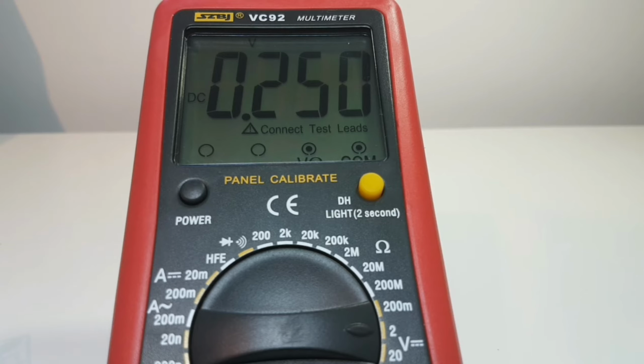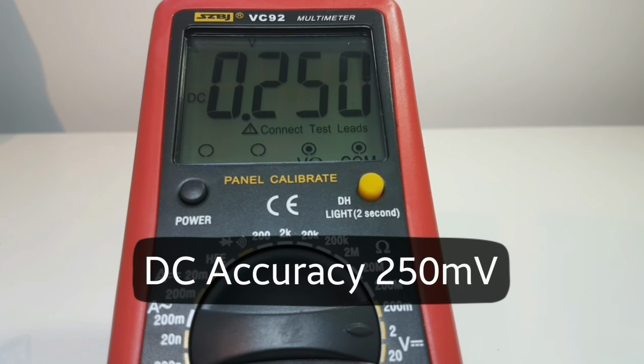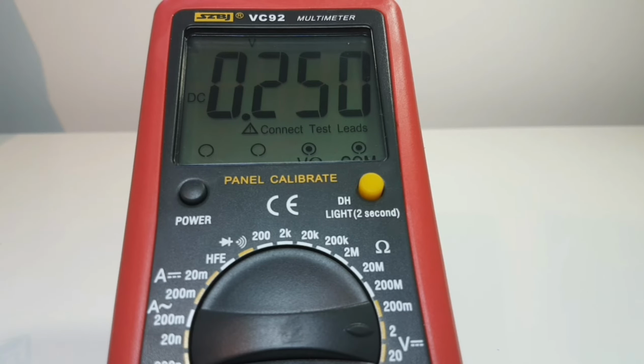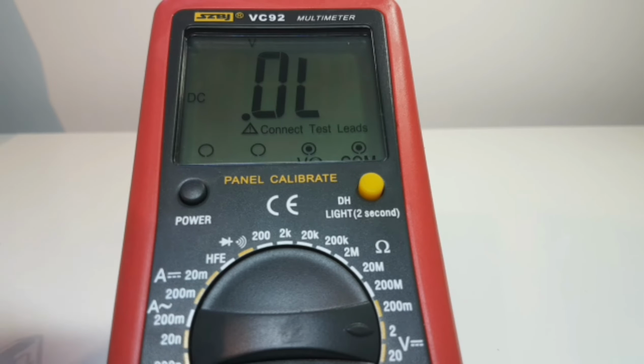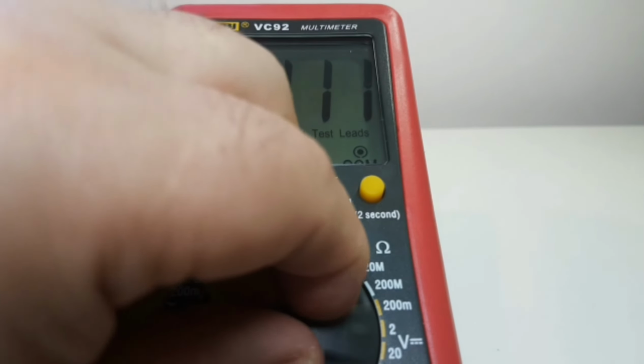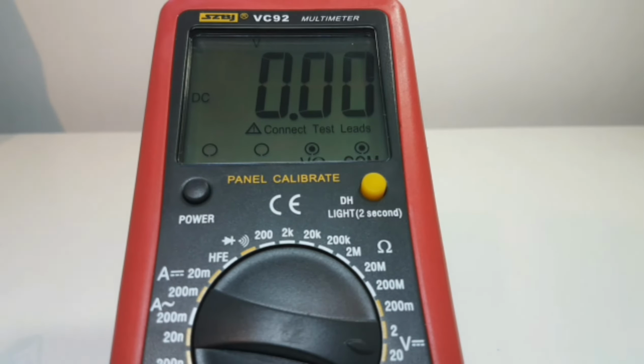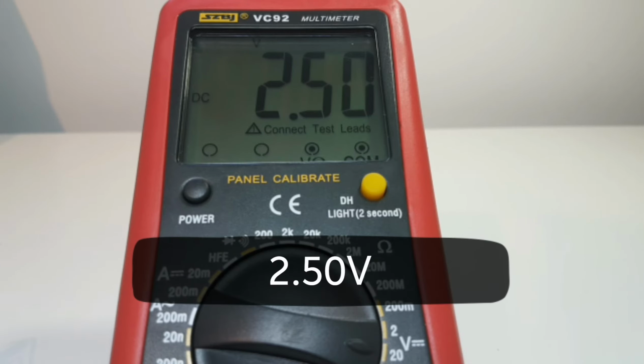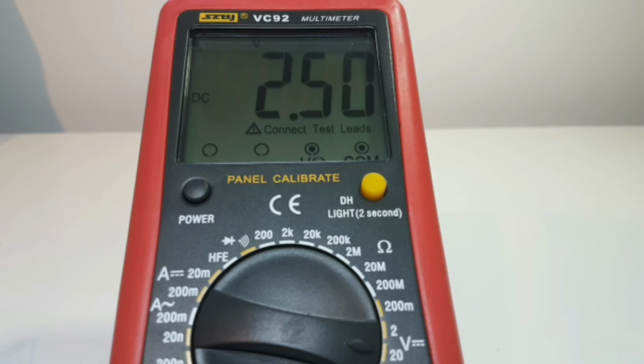Okay, let's get this party started. We are in DC accuracy mode right now. We are going to check the low voltage side of things. We should be looking at 250 millivolts, and as you can see, spot on 250 millivolts. We are OL because it is non-auto-ranging, so we have to take it up a notch. Are we going to see that 2.5? And look at that, spot on. So in terms of that low voltage accuracy, it is a win-win.